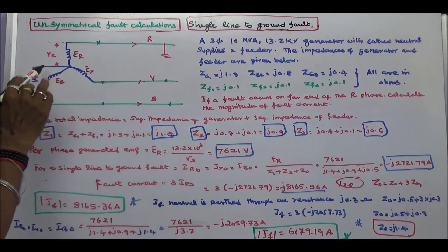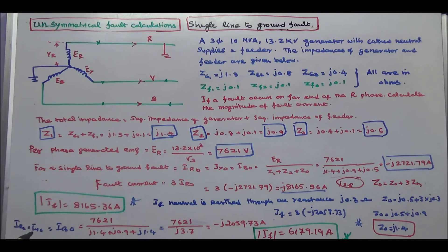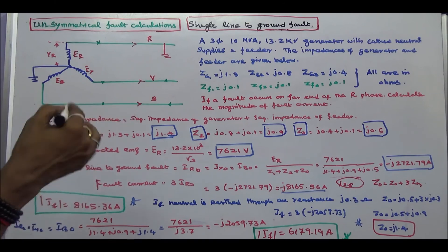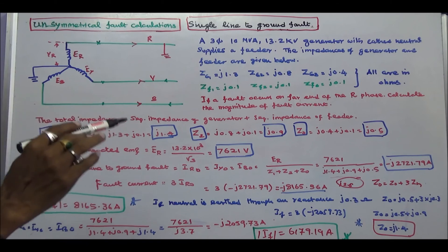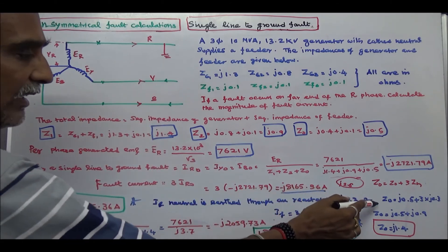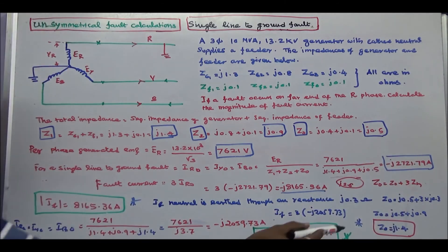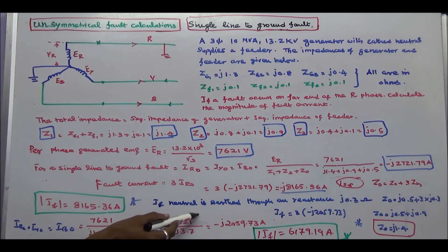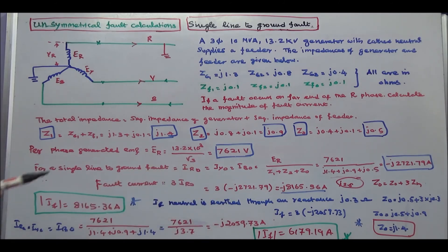The next question is: if the neutral is grounded through a reactance of J0.3 ohms, calculate the magnitude of fault current. Now the zero sequence current equals ER divided by (Z1 plus Z2 plus Z0 plus 3·Zn). Therefore Z0 becomes J0.5 plus 3 times J0.3, so Z0 equals J1.4. Therefore the zero sequence current equals 7621 divided by (J1.4 plus J0.9 plus J1.4), which is 7621 divided by J3.7, equal to −J2059.73 Amps. Fault current IF equals 3 times zero sequence current; the magnitude of fault current is 6179.19 Amps.